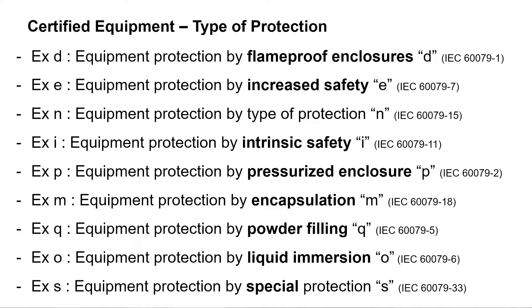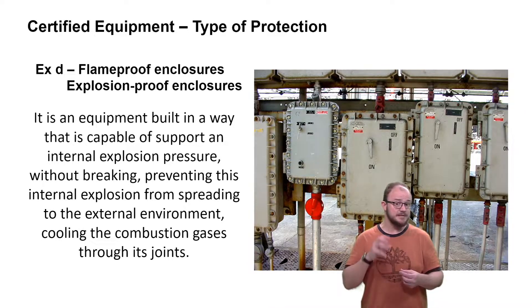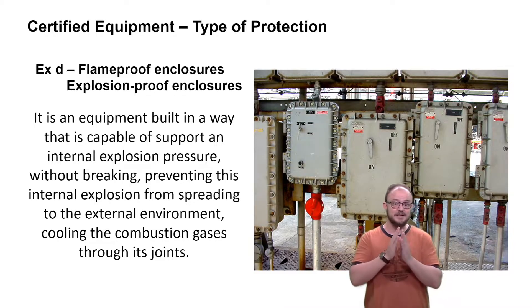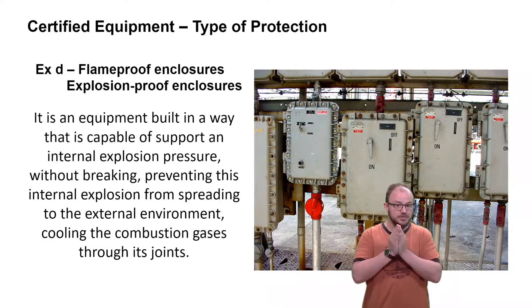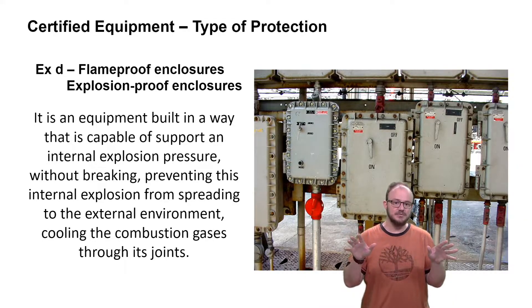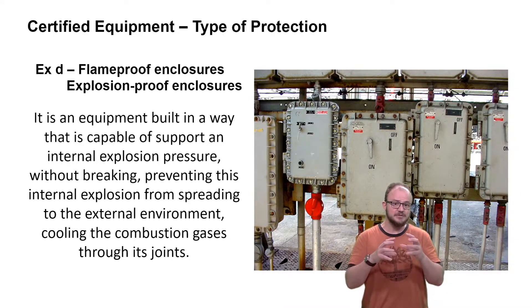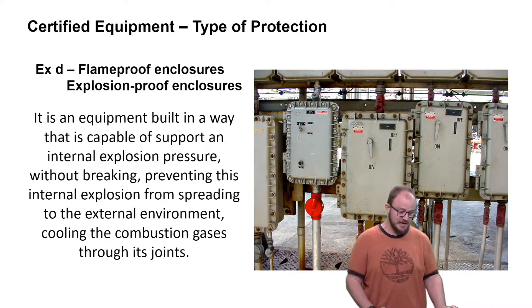The first of them is the flameproof enclosure, or explosion-proof enclosure. It's very interesting because the first time I heard about this equipment, I thought — wrongly — that everything around would explode and the equipment would be in one piece. That's quite the opposite. This type of protection supports internal explosions without having connection with the outside, and also cools down all the vapors and gases from these explosions through its joints. That's the function of this type of protection.